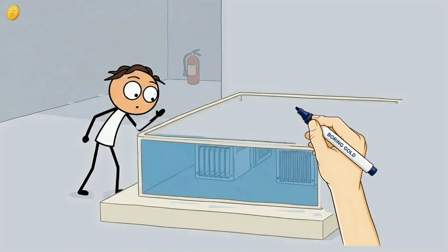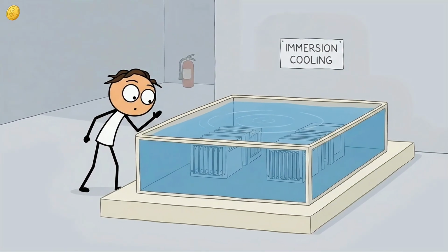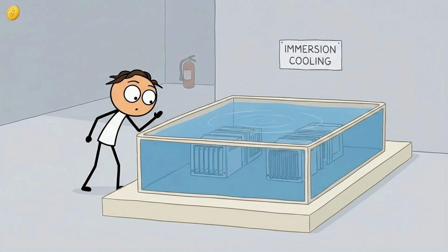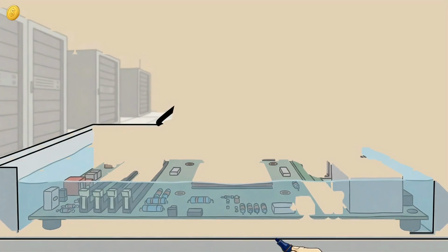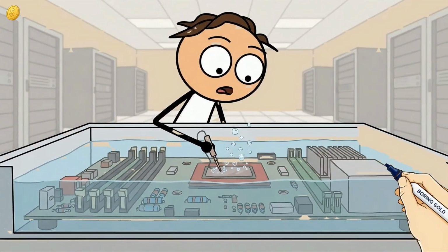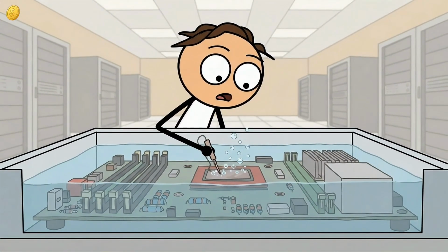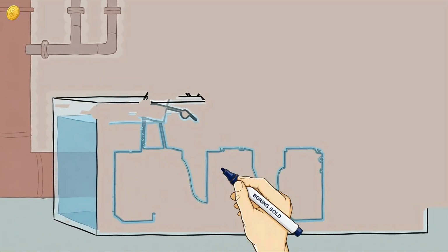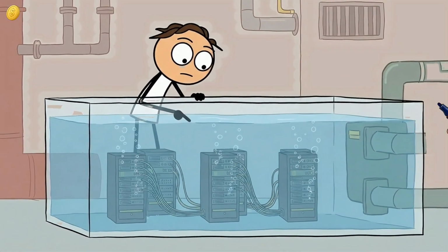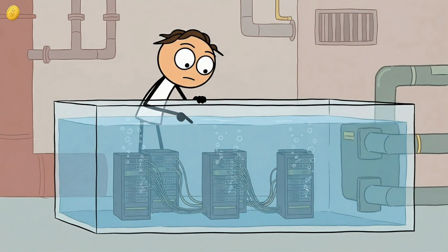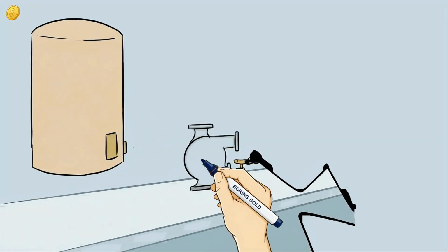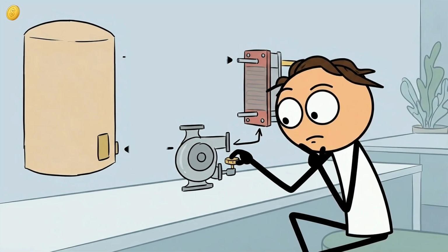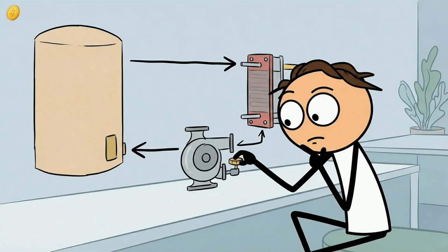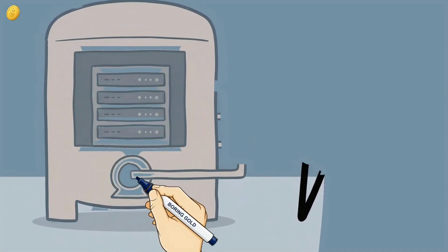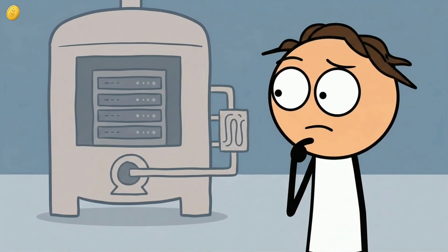There is also immersion cooling, which is exactly what it sounds like and sounds considerably more alarming than it actually is. Entire server boards, including the GPUs, are submerged in a bath of dielectric fluid. The fluid absorbs heat directly from chip surfaces and circulates through a heat exchanger. Immersion achieves PUE values approaching 1.03. The systems are mechanically simpler than DLC. There is just a tank of fluid, a pump, and a heat exchanger.